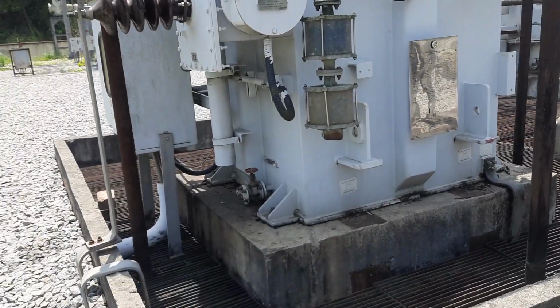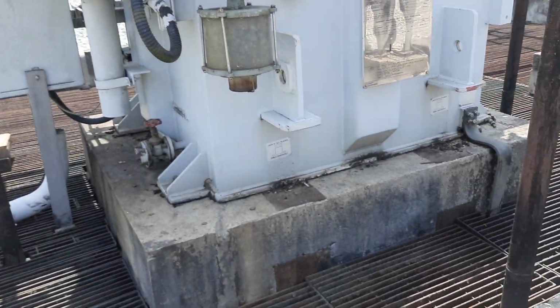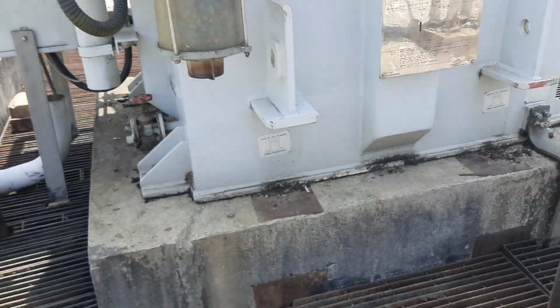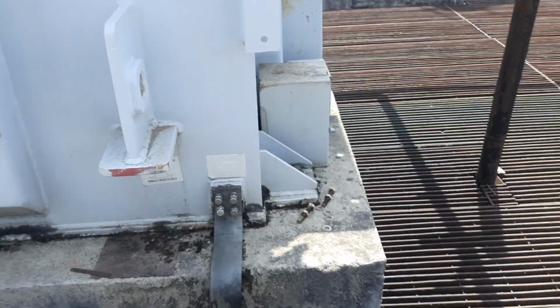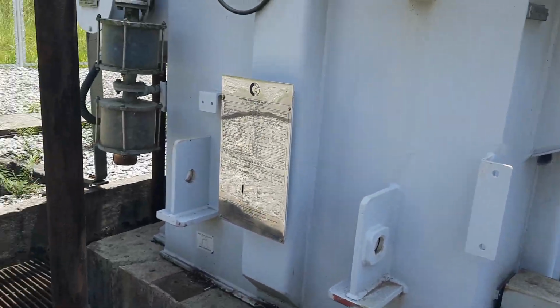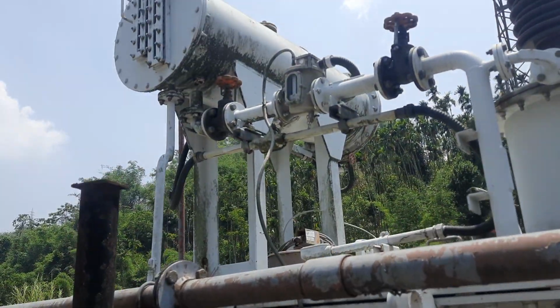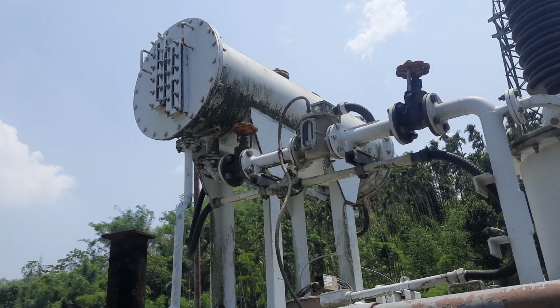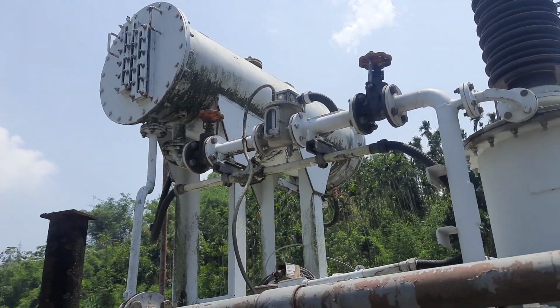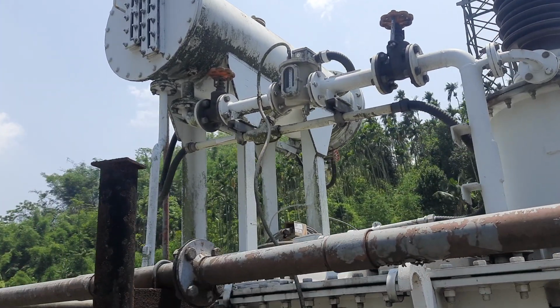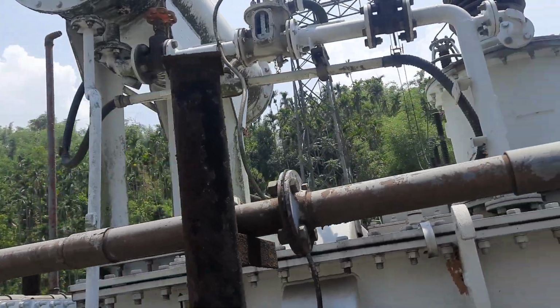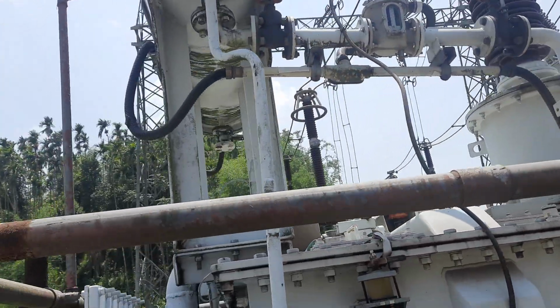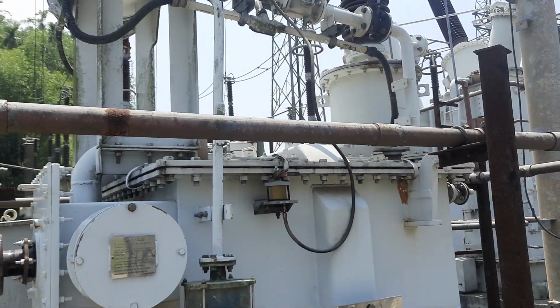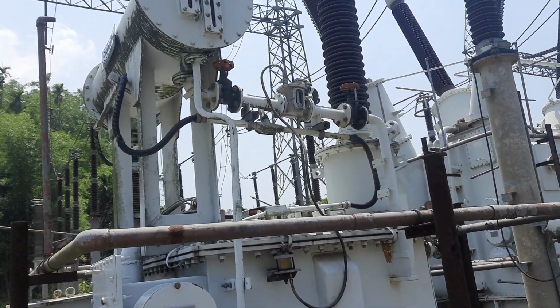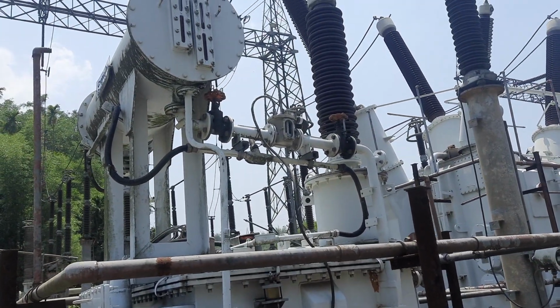So this is how the placement has been kept, directly on top of this structure, because there is not much vibration, as this is just a static device. Also one thing to remember is that the conservator tank has been provided on top to allow the expansion of the oil, because especially during daytime the temperature normally goes up, the oil expands, and to allow for that expansion we are providing this conservator tank.